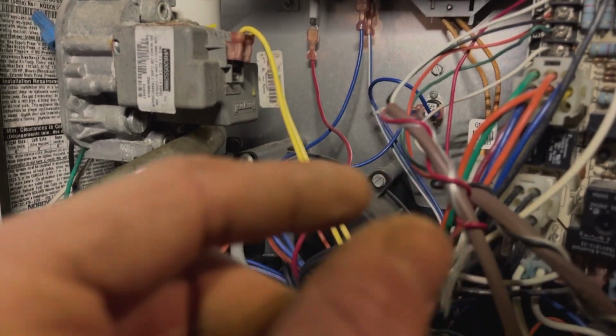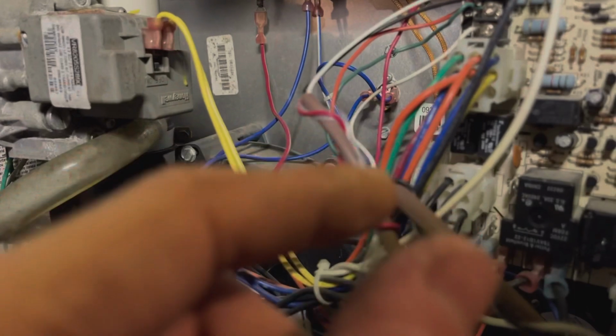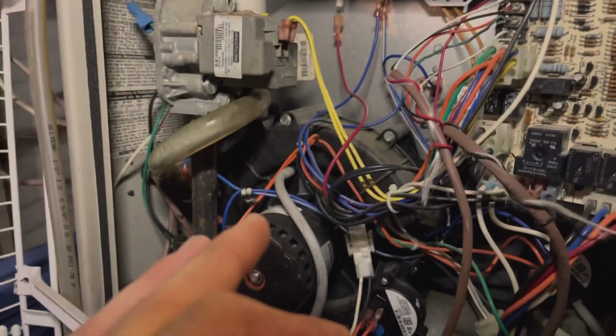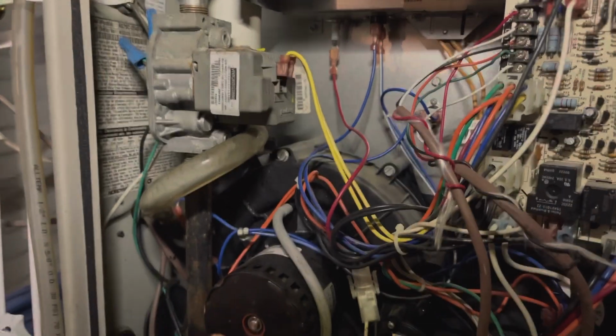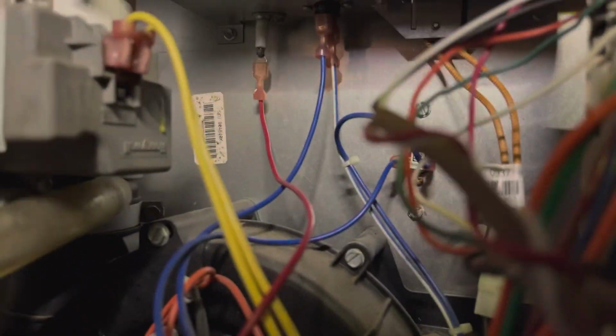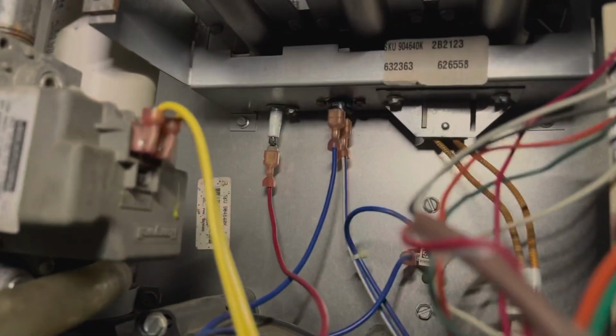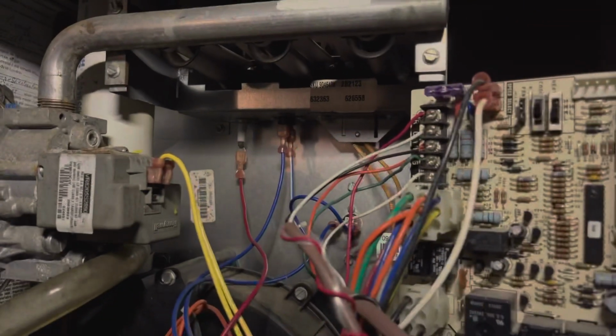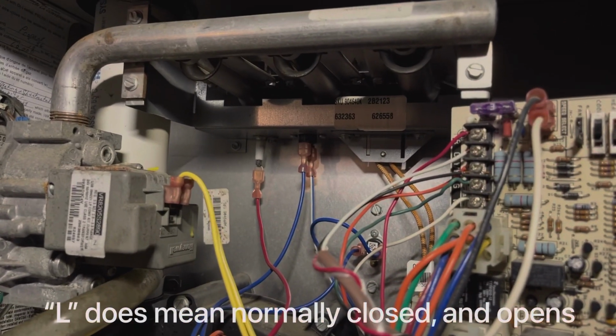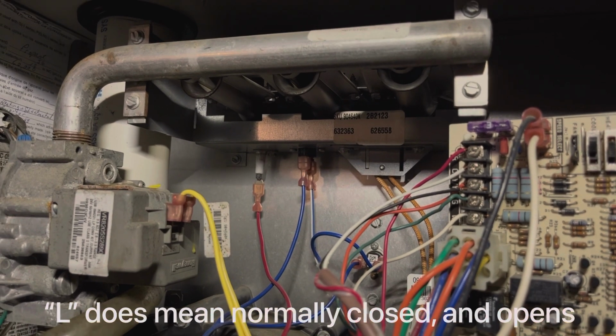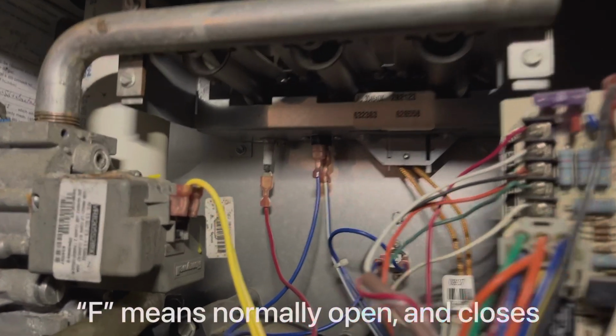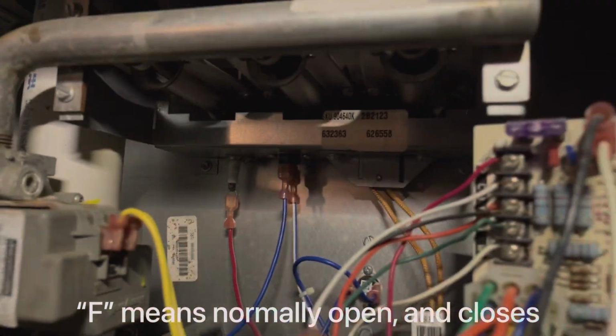And if you look up online, they mean two different things, whether they're meant to be closed and then they open, or they're meant to be open and then they close. So you could test whether there's continuity or not, and depending on the type of limit switch, then you know whether it's good or bad. I'm trying to remember exactly because I don't do this every day, but this one, L, I believe L means it's meant to be closed, and then it opens, and this one was stuck open with that little button there.